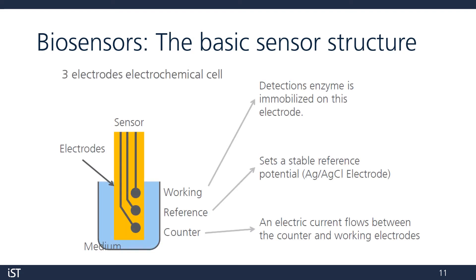Now, let's take a look at a typical enzymatic biosensor. Here we have a simplified version of the IV-4 strip type sensor from iST Technologies. There are different variations of biosensors which we'll discuss, but almost all of them rely on this measurement principle. The three key components are the working electrode, the reference electrode, and the counter electrode. The enzyme is deposited and immobilized on top of the working electrode. The reference electrode sets a stable reference potential, and an electrical current flows between the counter electrode and the working electrode.